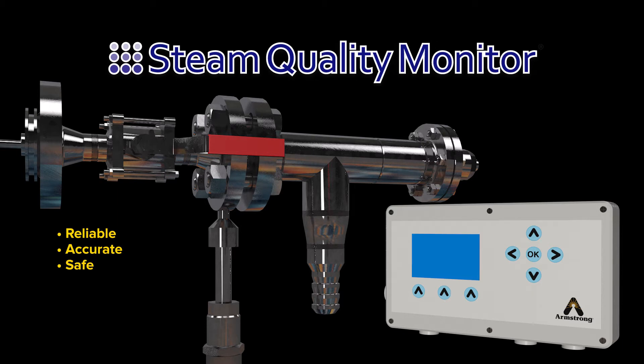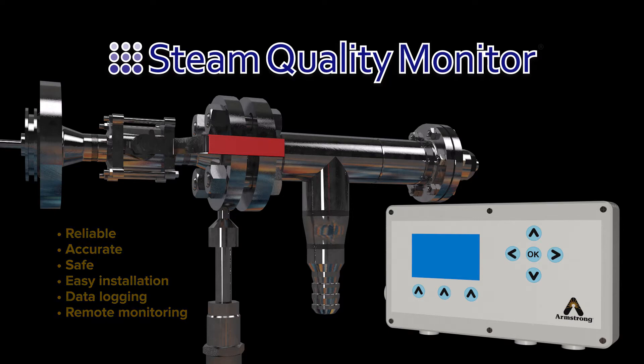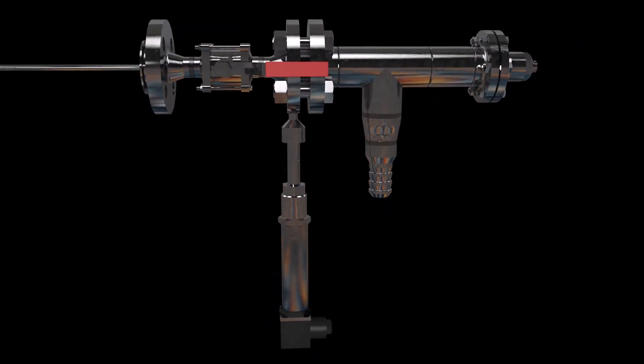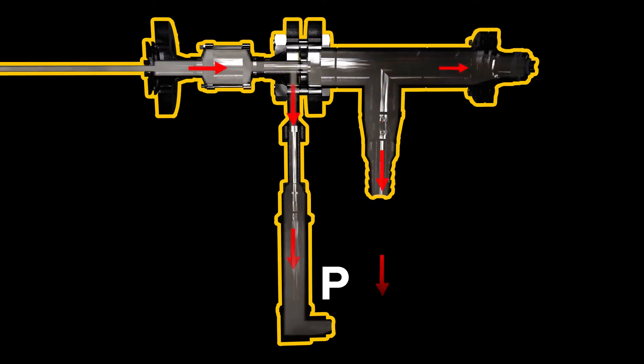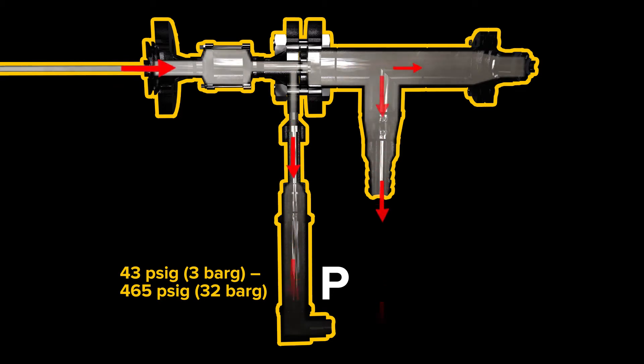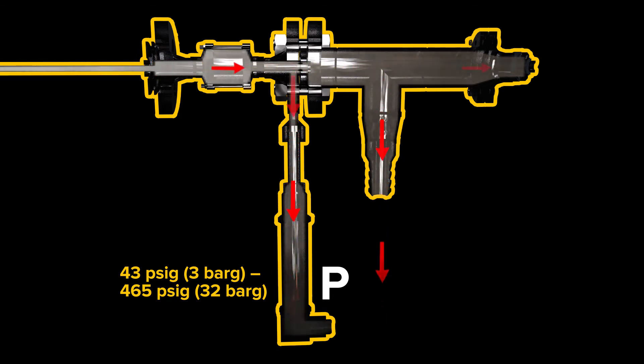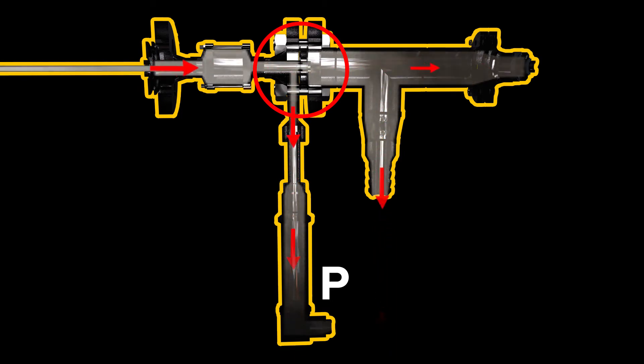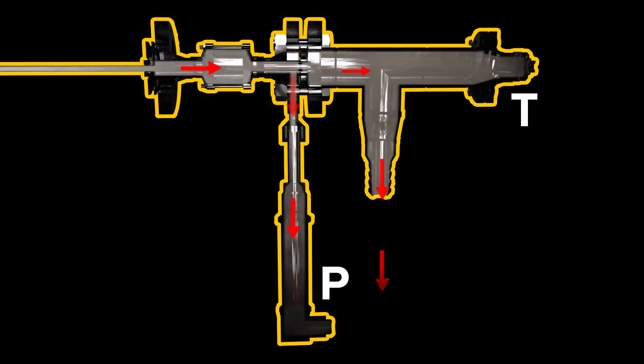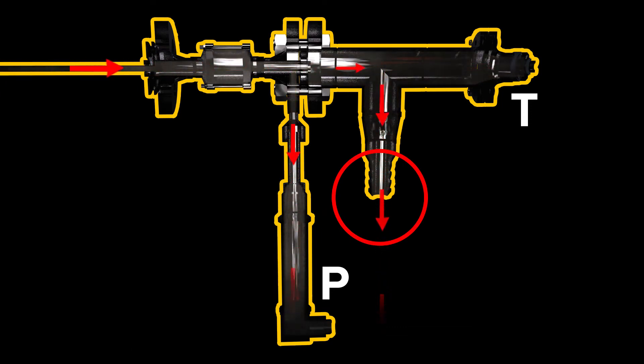The Steam QM1 is reliable, accurate, safe, easy to install, and it provides you with data logging and remote monitoring capabilities. The Steam QM1 monitors and measures dryness fraction and alerts you of steam quality problems. Steam enters the QM1 at any monitoring point on the steam network. The first check is at pressure sensor P. Incoming steam is between 43 and 465 pounds per square inch gauge, or 3 bar to 32 bar gauge. Steam enters through a calibrated orifice, and this restriction reduces the pressure to atmospheric pressure. The temperature sensor T then monitors temperature, and finally the steam sample is discharged to an atmospheric drain.